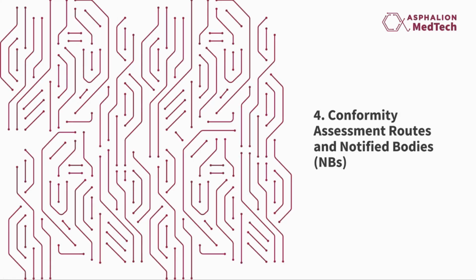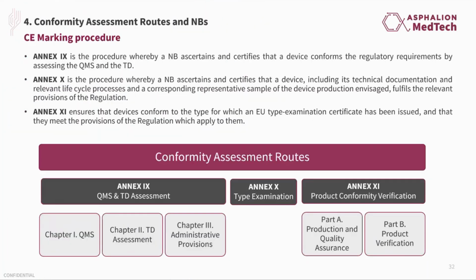So to finish this first section, we will talk about conformity assessment routes and notified bodies. Okay, so once we know that our product is a medical device, all applicable rules to it, and its final classification, we must focus on the available conformity assessment routes included in MDR for each device class. The routes are the following: Annex 9, Annex 10, and Annex 11.